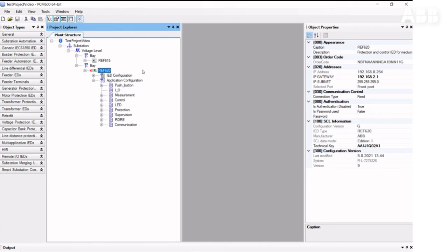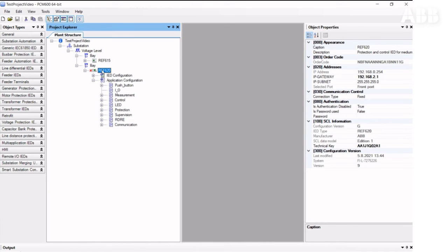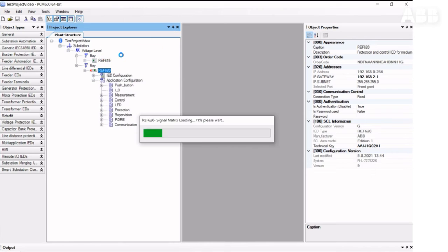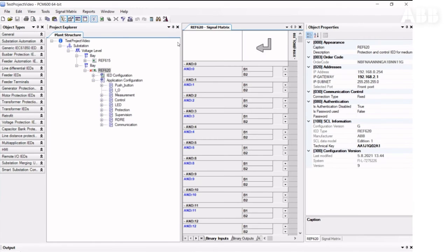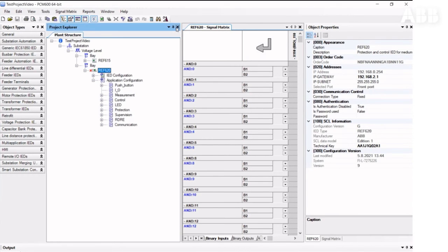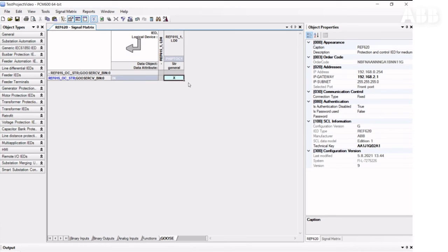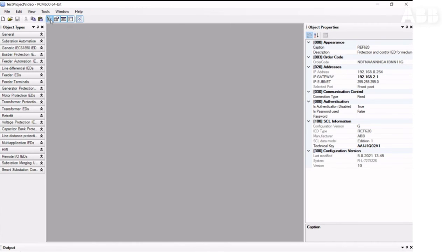To finalize this configuration on the receiver side, we need to go into the Signal Matrix tool, open up the GOOSE tab, and connect the signal we're receiving to the GOOSE receiver function block in the configuration. In the real project, you may have many more signals on top, so you need to have the right number of function blocks in the configuration to receive these signals. Then we save and close the tool.